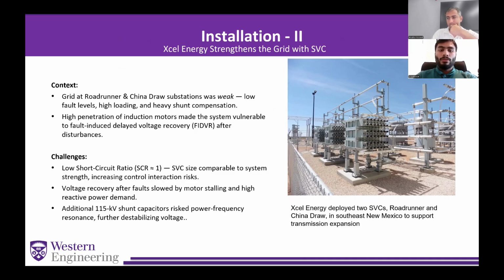And it also has a problem of voltage recovery. Voltage was recovered slowly due to motor loads and high loads in that station. These loads demand high reactive power. To cater to this problem, they installed two different SVCs in these two substations. Next slide, please.